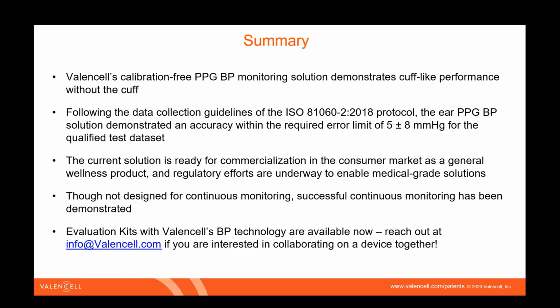But this is another thing that's important to point out. One other thing Valencell did is in the ISO test. Remember how I told you all there's 8 measurements you take in this test. Well, up to 8 measurements you can take, and we took all 8. We're just going to take all 8 measurements back to back. Might take a whole hour for this person, but we're going to take 8 measurements back to back with the auscultatory cuff, the oscillometric cuff, and the earbuds, and all the other sensors that are there. And so we did this.